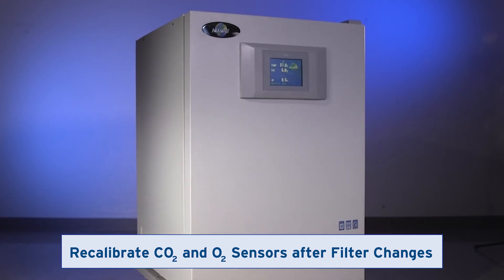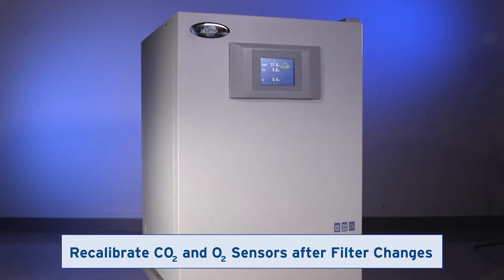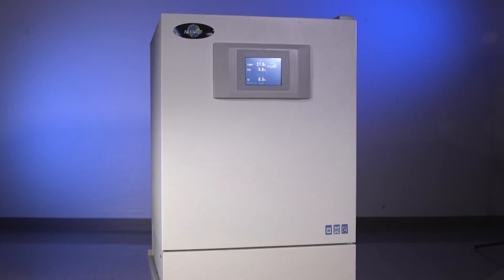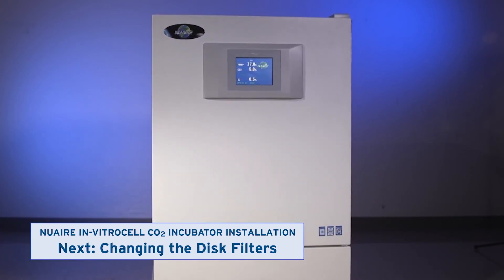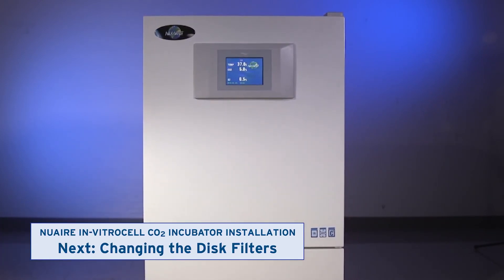When done maintaining all filters, it is best to recalibrate the incubator's gas sensors. Watch the next video to learn how to change the gas and air disc filters.